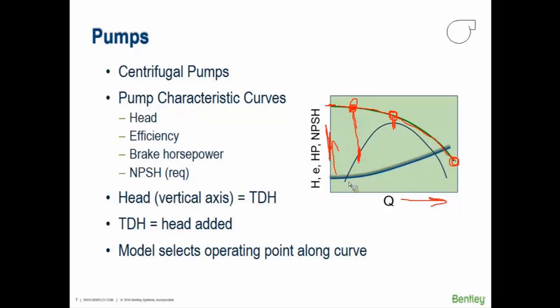There are additional curves to consider: a horsepower curve, an NPSH curve, and a system curve. As you increase flow through a pipeline, head loss increases. Where the system curve intersects the pump curve is the operating point. A steep system curve means multiple force mains; a shallow system curve means a large diameter pipe, allowing the pump to deliver more flow.